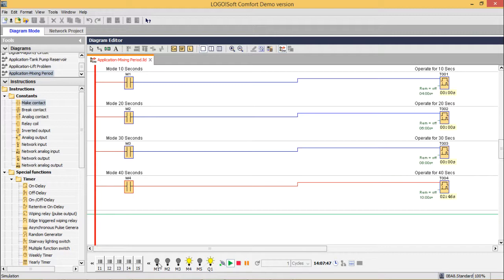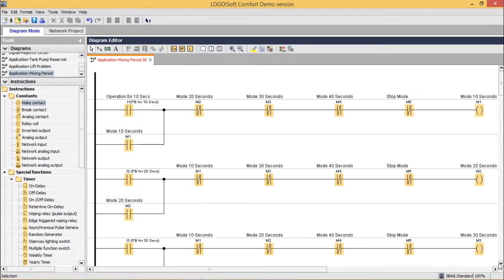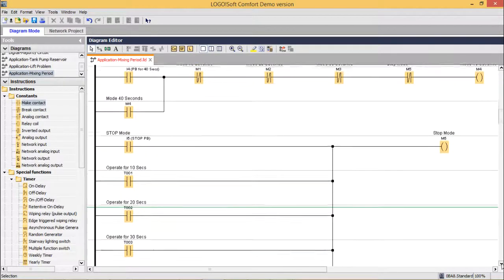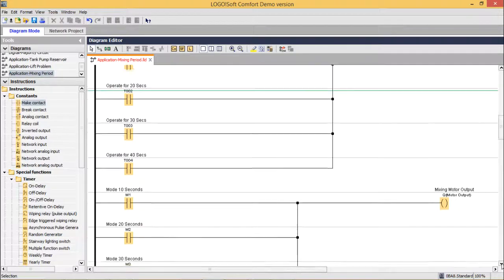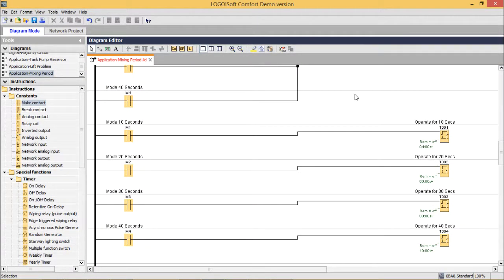For I1, the mixer operates for 10 seconds. Pressing I2, I3, or I4 during this time has no effect, and pressing I1 again also does not interrupt it. When it is in operation, pressing the stop button stops the motor. Using simulation, we have verified the circuit works correctly. Try implementing the same circuit with a different logic to develop your logical thinking. You can pause the video to study the ladder diagram and gain ideas for solving unseen problems in your career. Leave any comments or doubts below, and thanks for watching.